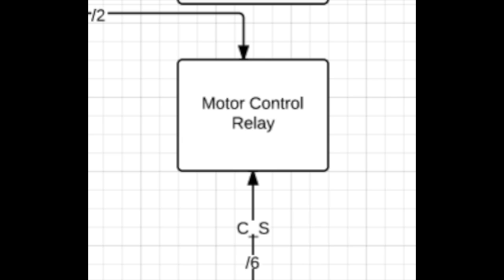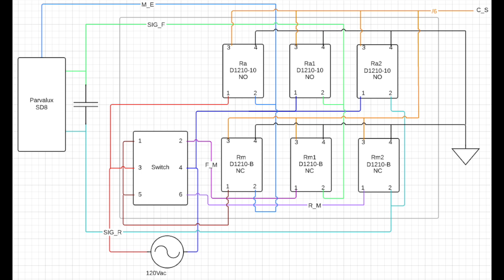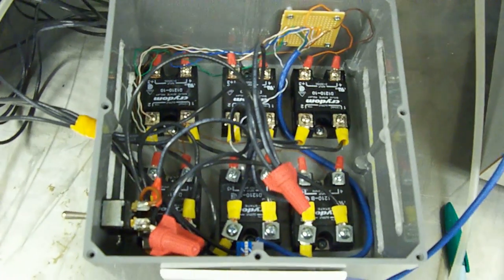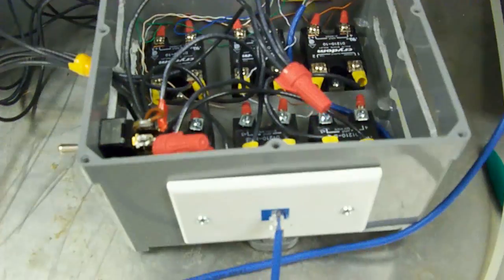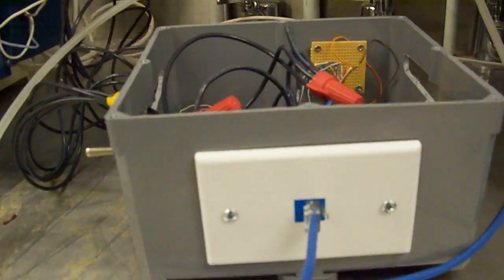There are two types of relays, which are normally closed and normally open. The normally closed relays are used in conjunction with the switch to maintain manual operation. When a test is being run, these three relays are sent a control voltage that opens them, disabling the manual switch. The other three relays are normally open. During automated testing, these relays receive control signals that close the relays that correspond to the correct motor direction.